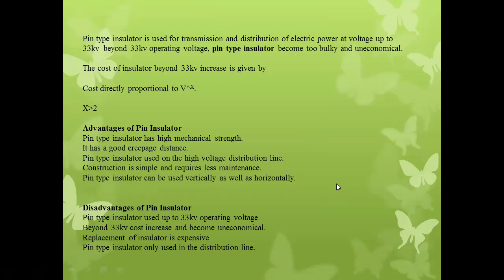Next, disadvantages of the pin insulator. Pin type insulator is used up to 33 kilovolt operating voltage. The operating voltage is limited for the pin insulator because if you want to use it for higher voltage greater than 33 kilovolt, you have to increase the number of shells. If you increase the number of shells, the pin insulator becomes too bulky and at the same time uneconomical. That's why pin type insulator is used up to 33 kilovolt.